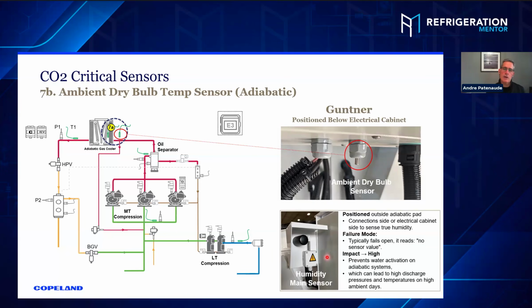I don't know enough about it if the text can flip back and forth or not, but their humidity sensor is positioned outside the adiabatic pad, connection side or electrical cabinet side, so it can sense true humidity. The failure mode, if it does fail, it fails open. And the impact is high, because if that humidity sensor fails, it prevents water activation on the adiabatic system.